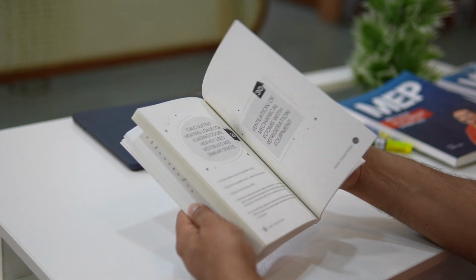Cooling load calculations - I have done a special video for cooling load calculation too. For example, a 10 floor building with 20 or 50 bathrooms, and how many taps are there, based on the height of the building, how you will select the pump capacity - booster pump, transfer pump - everything you can design. You can select the head, pressure, and horsepower needed, all calculated with the help of these equations.